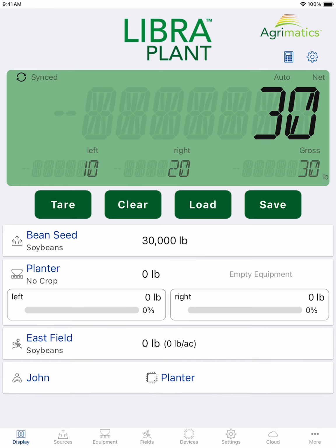From there, we want to go on to our Display tab and make sure that our weights are making sense. So again, paying attention to whatever channel you're currently working with, you would apply a known weight to that channel, either your body weight or a bag of something that you know how heavy it is, whatever you've got to do. And then we're going to want to make sure that those weights make sense. And if they check out, you can go right into calibration.